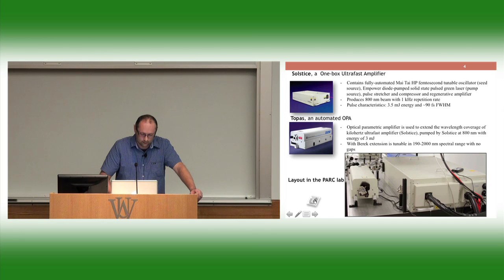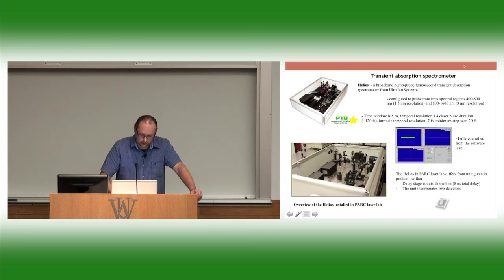That part we use just for transient absorption spectrometer. Here is our transient absorption spectrometer, Helios. Helios is made by Ultrafast Systems. Our version is way more complicated than the factory flyer. We have two detectors that are used for two different spectrum ranges: one for visible, second for near infrared. We have much longer stage to provide the delay between pump and probe beams. It's so long that it cannot fit inside the box, it's actually outside.